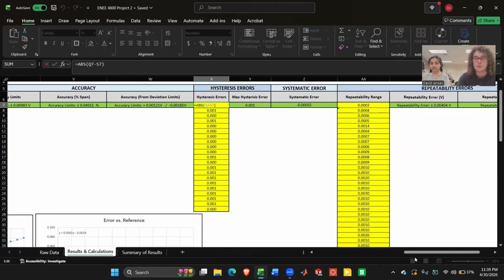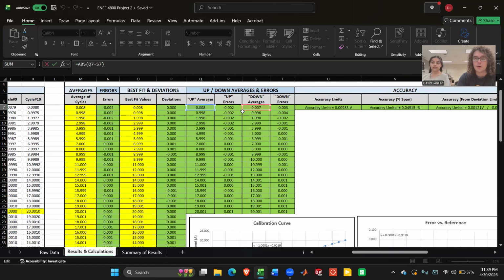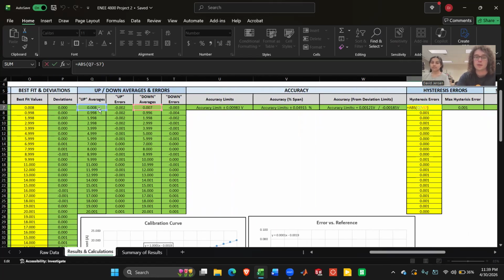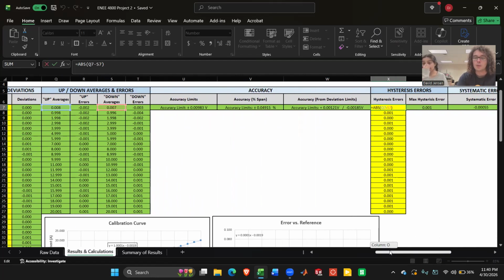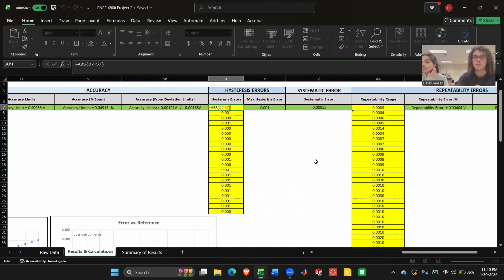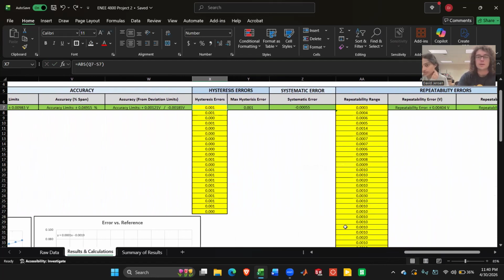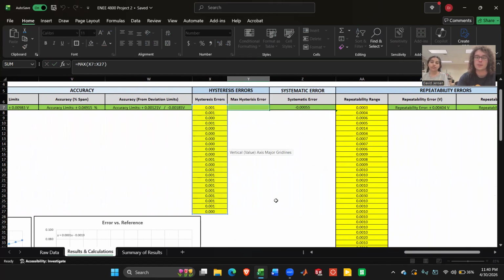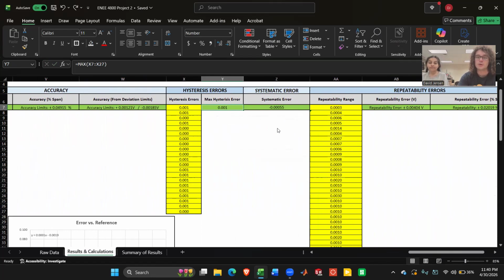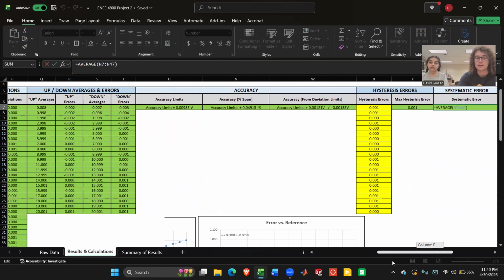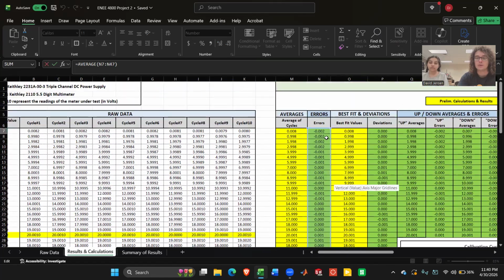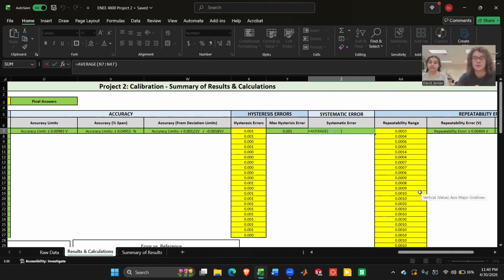The hysteresis errors were found by taking the absolute value of our up minus down averages. It doesn't matter which way you did them. It's essentially just the difference between the measurement in the up cycle and the down cycle. So we did that for each of the reference points, and then we used a max function to find the max value of that, and that is the accepted hysteresis error for this device. The systematic error is simply the average of all our errors that we found for each reference value here. And that was found to be negative 0.00055 volts.